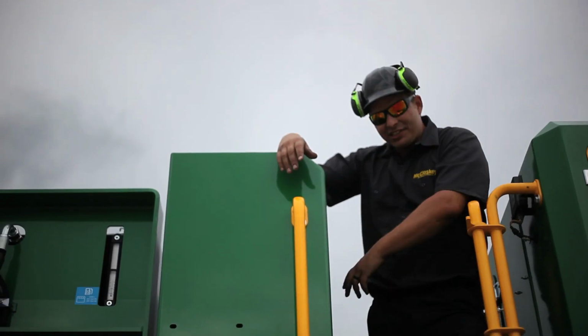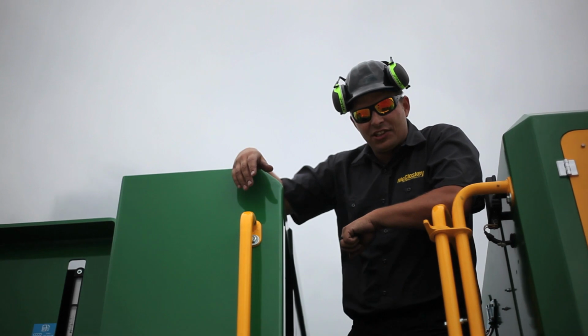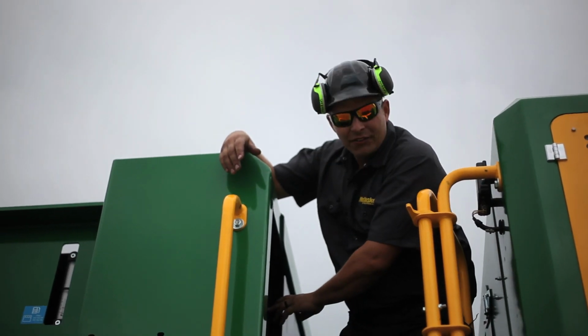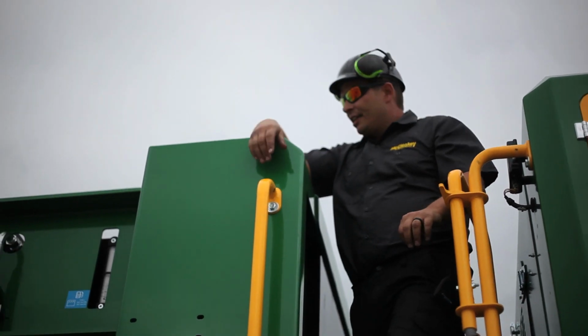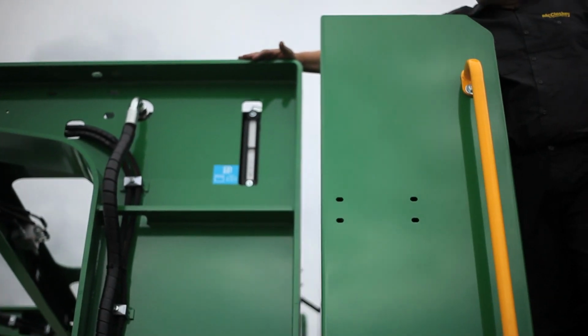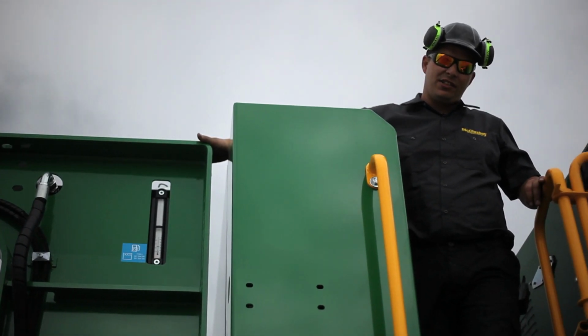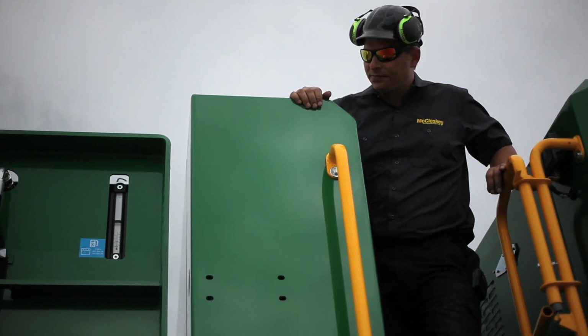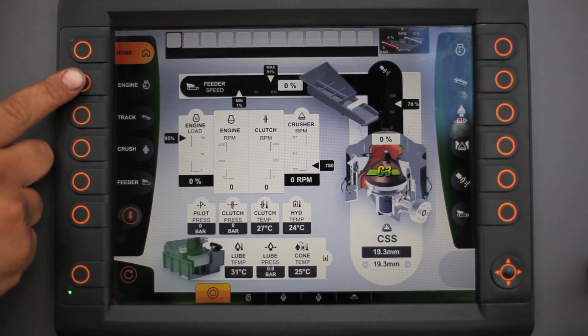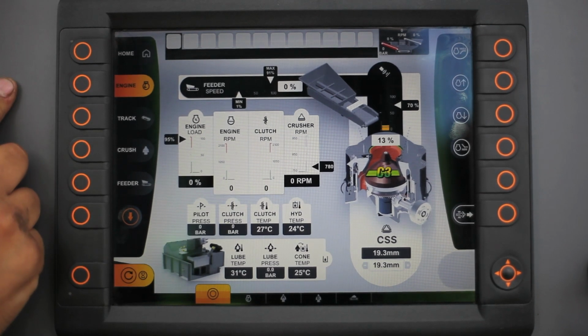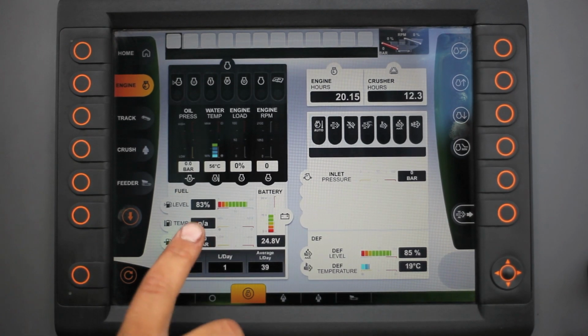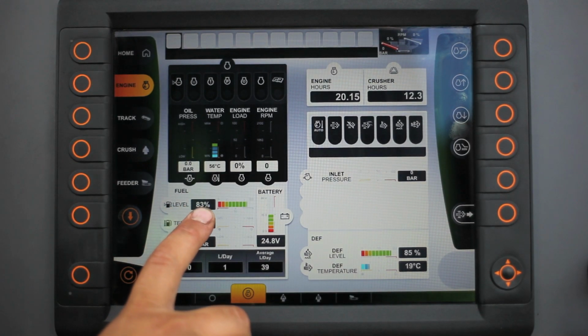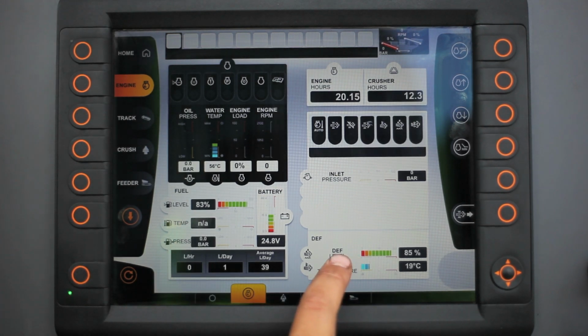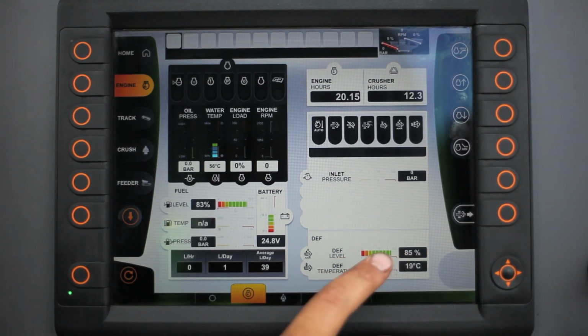Okay, another one of our checks is going to be to physically check the sight glass on the hydraulic tank, make sure that our level is in the sight glass. We also have our diesel tank to the right of it here, and we're just going to double check that we do have diesel in there as well. We can also check our diesel level on the panel. From the home screen, we're going to want to come down and press the Engine button. Once we've done that, we're just going to verify that our fuel level, which is at 83%, and we're going to verify our DEF level, which is at 85%.